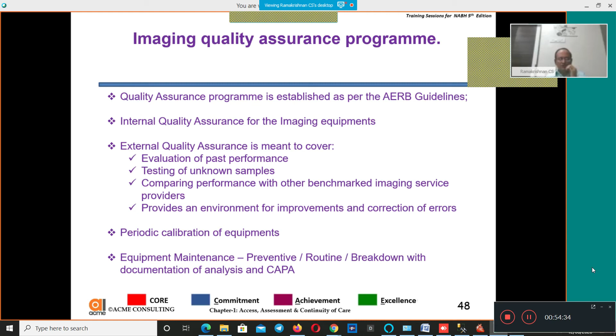Periodic calibration of equipment, even here the requirement, maintenance for all your remaining equipment to be done, with appropriate documentation. And wherever a breakdown has happened, we need to have a preventive mechanism in place. It means root cause analysis, corrective action, so that it's not repeated again. In fact, most of the breakdowns are prevented by appropriate maintenance and routine checks, also using checklists. Right?